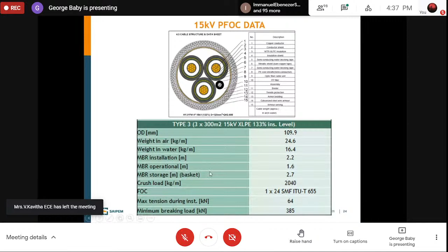So this is the cross-sectional view of a 15 kV power and fiber optic cable. It's a 3-core cable, and there is a fiber optic core as well. Here, this 15 kV cable, you can see it's 110 mm, like 11 centimeters, that's how big it is. And this is the weight of the cable in the air, 24.6 kg per meter. The same is given for in the water. As you know, the weight of any product will be less in water. And there is a minimum bending radius, which is quite important, because if you bend beyond this minimum bending radius, it will affect the integrity of the cable and lead to fatigue damage.